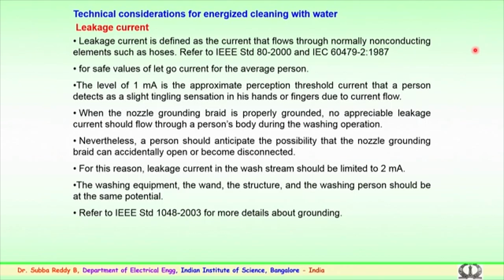So, the washing equipment, the wand, the structure, the washing person should be at the same potential, that is to be noted. So, the person who is standing at the tank arrangement which is being used for cleaning the insulator during live line condition has to be at the same potential, so that the rise in potential is not seen and the safety of the personnel who is cleaning the insulator has to be taken care of.